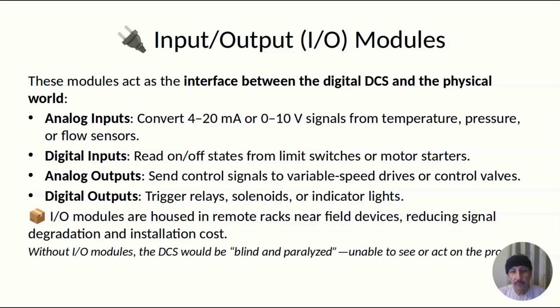So while I/O modules might seem like passive components, they are actually foundational to the entire DCS architecture. They enable the system to perceive and act, making real-time closed-loop control possible. As the saying goes, without I/O, your DCS is blind, deaf, and paralyzed, and no amount of computing power can compensate for that.